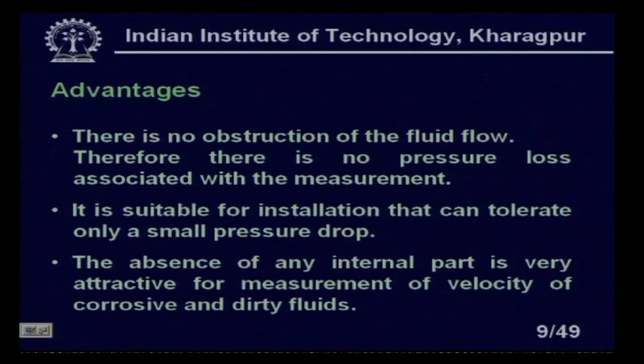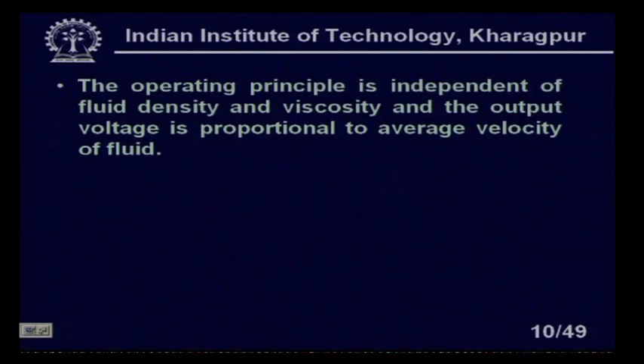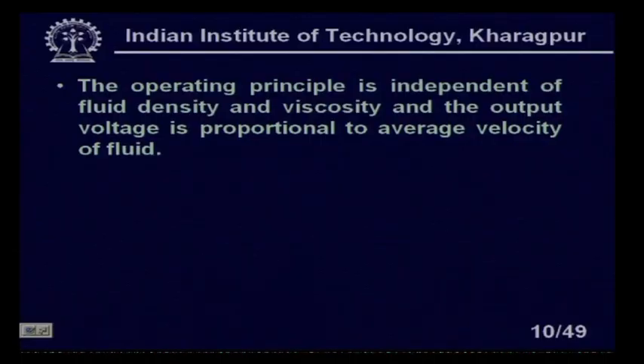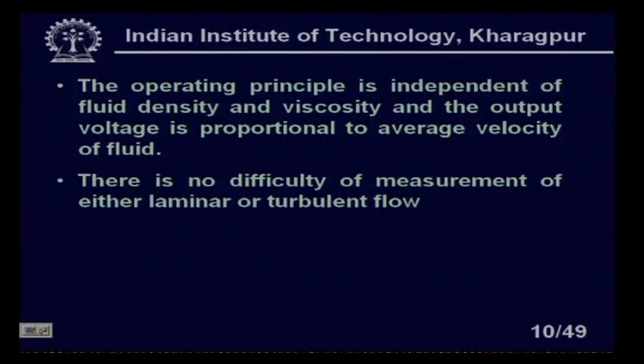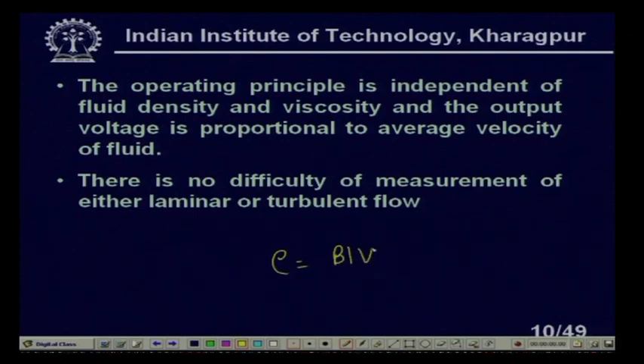The operating principle is independent of fluid density and viscosity, and the output voltage is proportional to the average velocity of the fluid. This means it is suitable for measuring both laminar and turbulent flow. However, for different liquids at the same velocity, you will not get the same output voltage, because the equation E = V·L·B shows that as the material of the fluid changes, the relative permeability mu_r changes, changing the flux density B and thus the output.